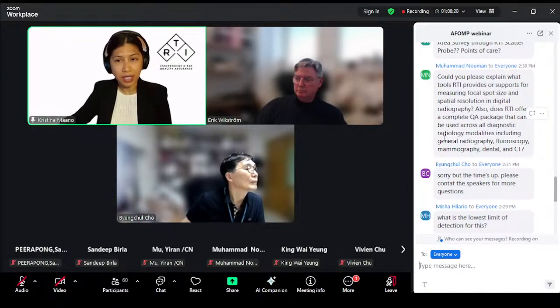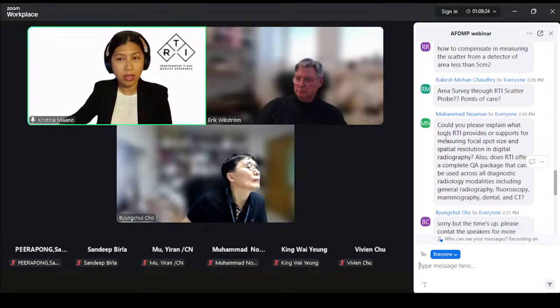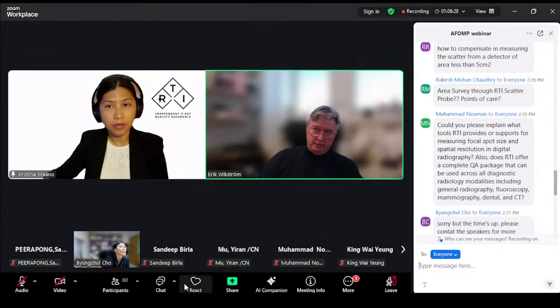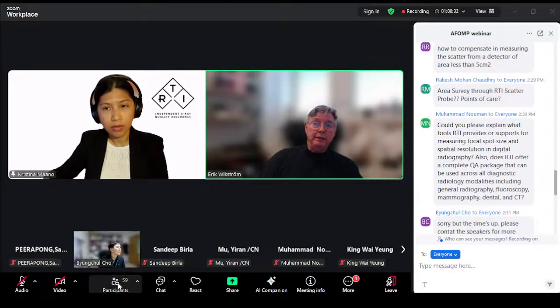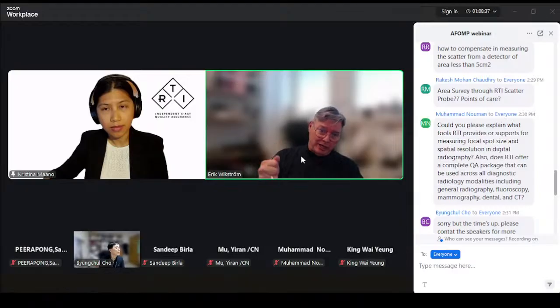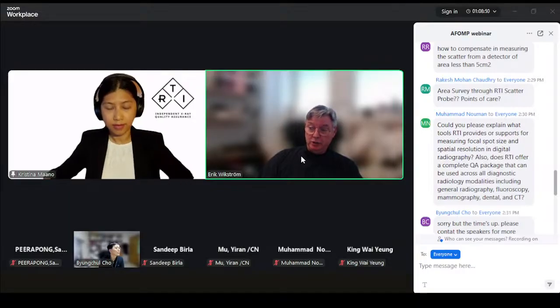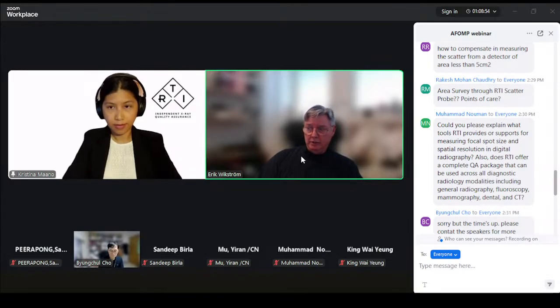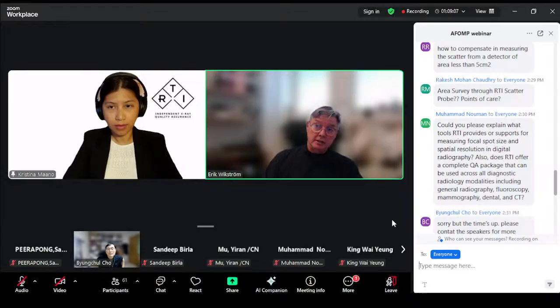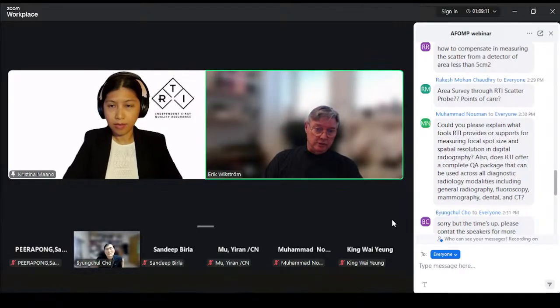Area survey through the RTI scatter probe. Points of care. An area survey would be okay, and that would be looking at door jams, looking at the throughput through a wall and stuff like that, and that's fine. It has the sensitivity for it, so that would be one part of work that could be done. Points of care, well, I don't really know what the questioner meant by that. If that has to do with what we need to watch out for, we recommend calibration every 2 years, and normal care for an instrument. Don't drop it, and be a little bit careful with it, and that's about it. So it's a comparatively robust instrument.